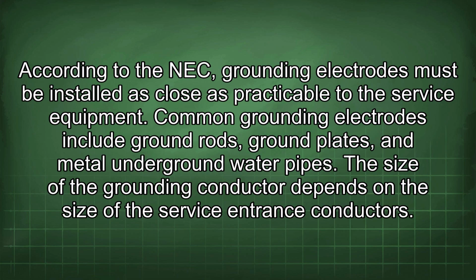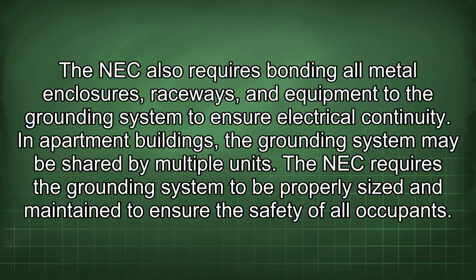According to the NEC, grounding electrodes must be installed as close as practicable to the service equipment. Common grounding electrodes include ground rods, ground plates, and metal underground water pipes. The size of the grounding conductor depends on the size of the service entrance conductors. The NEC also requires bonding all metal enclosures, raceways, and equipment to the grounding system to ensure electrical continuity.